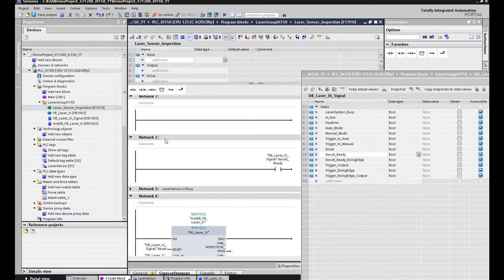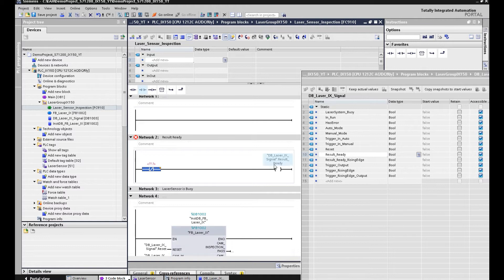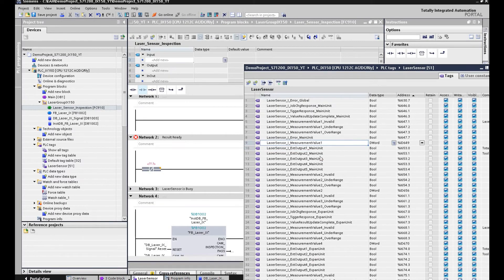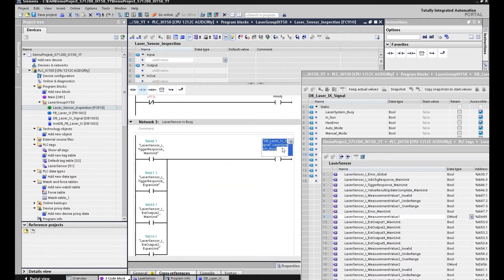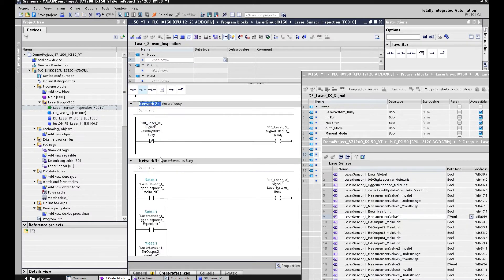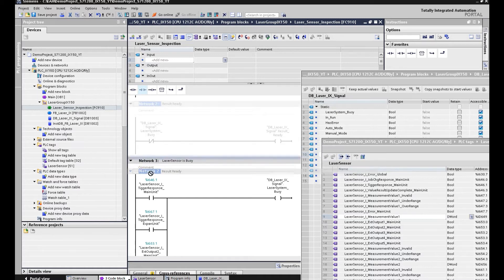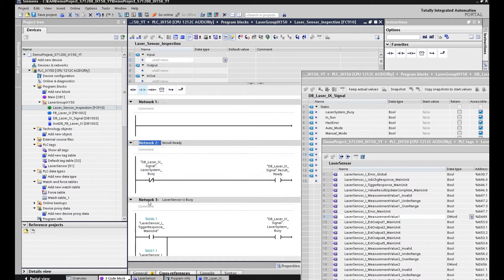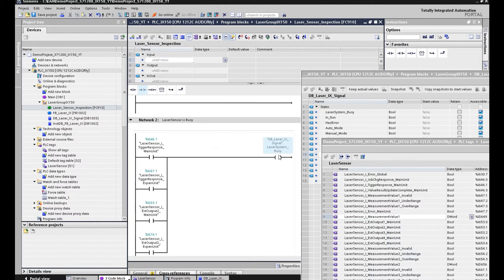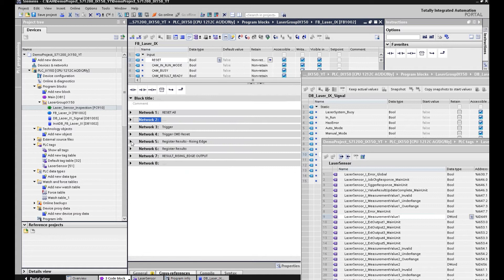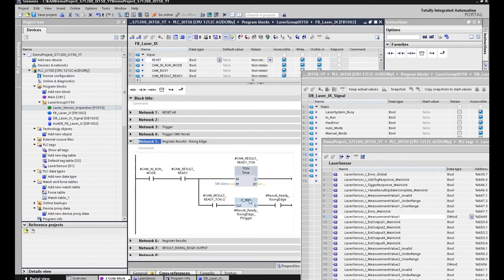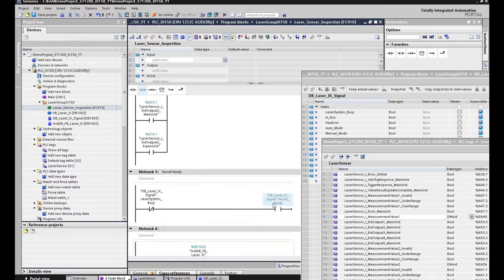Go back to our logic — this is the result ready. How to define this result ready? We go one step before. Some logic controls this result ready. If the system is not in busy mode, we can see the result is ready. This busy is organized so that it should be on top. When the system is not busy, we say the result is ready. Because in the function block we use the rising edge — not busy rising edge to register the result — so we use not busy as the result ready signal.